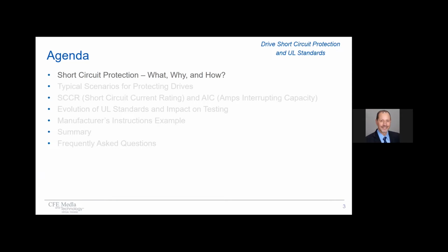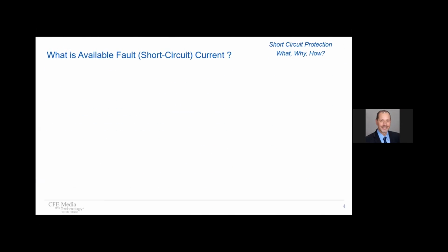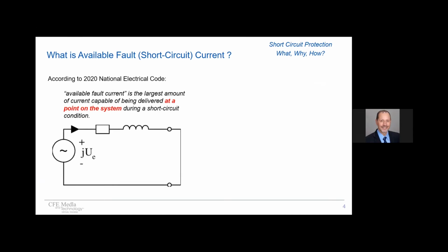Let's start with the basics of short circuit protection. First of all, let's look at this thing called short circuit current. A main concern when connecting equipment is to understand how much current can flow in the event of a short circuit. As of 2020, the US National Electrical Code standardized on the term available fault current. And available fault current is simply the largest amount of current capable of being delivered at a point on the system during a short circuit condition. And I'll stress, at a point on the system.